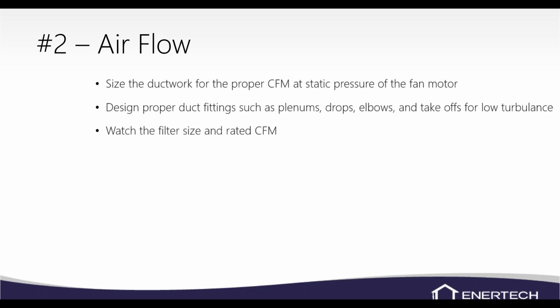Make sure you're watching your filter size, the MERV rating on it, and the rating CFM. Some of these filters have quite a large pressure drop across them, so just be careful with some of the ratings on your air filters.